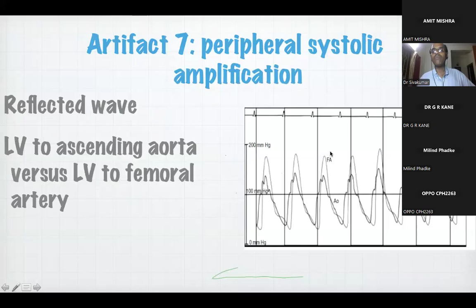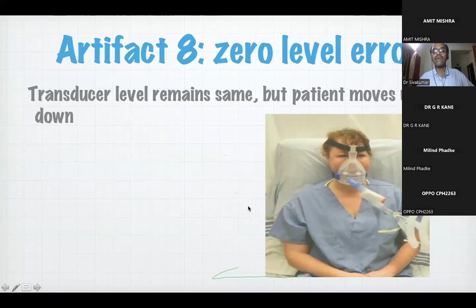Peripheral systolic amplification, we all know about it. It is due to the reflected waves coming. The more peripheral you are, the higher your systolic pressures are going to be. Zero level error: you would have started the pressure tracing with the patient lying down. But as the patient develops pulmonary edema and you are lifting the patient up with a pillow, you are not changing the zero, the transducer level. So this will give what is called zero level artifact.